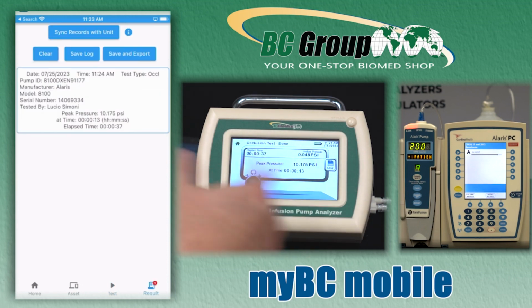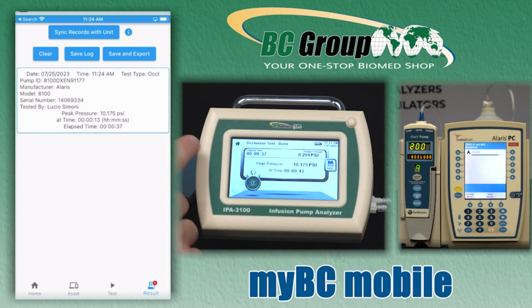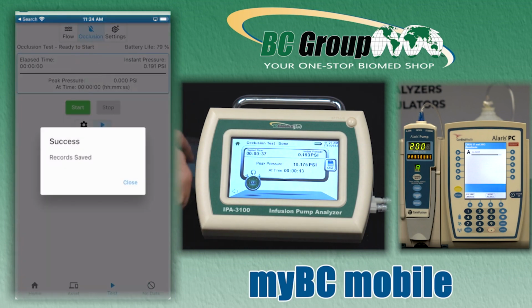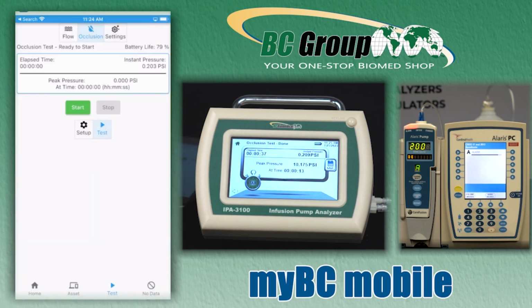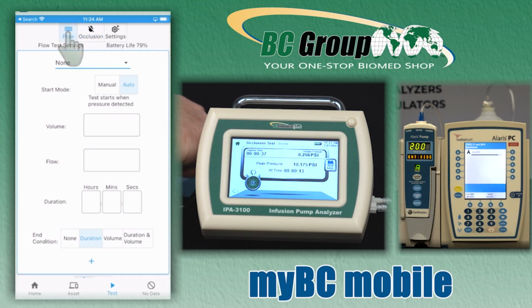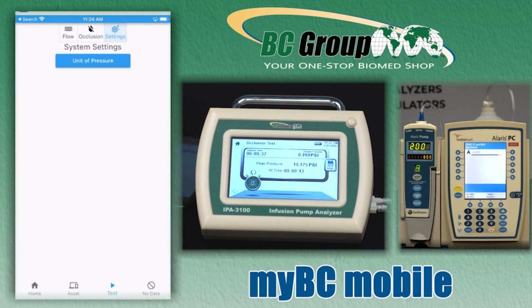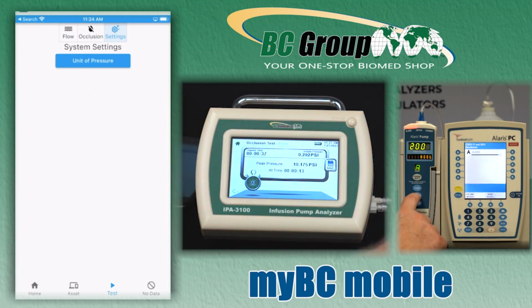And we can see the pump in the background, the IPA, just eliminated that pressure that had built up. And now we have our test results, same as before. We can save it to our log. So that's been saved. Now I can run another test or go back to flow testing, do more occlusion testing, or in the system settings, I can change which pressure. I'm going to go ahead and turn off this pump.